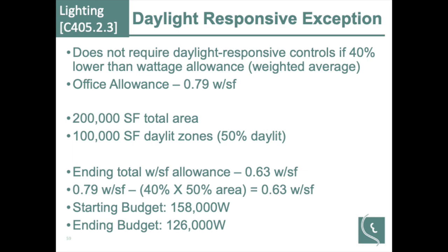So here you can see, as long as my total installed power for lighting for the building is under 126,000, I'm done with daylight harvesting controls. I don't have to buy them, I don't have to install them, I don't have to maintain them, and I don't have to commission them. So that's where it's just a weighted average across the whole building. It doesn't necessarily mean you have to reduce 40% in that specific area. You can do it across your whole building. So in this example, I just have to be 20% less because my daylit area is only half of my total square footage. So it's a weighted area average.